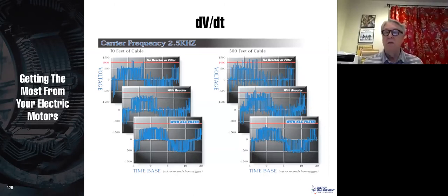DVDT, of course, stands for differential of voltage with respect to time, or derivative of voltage with respect to time. All it really means is it reduces the rise time. DVDT means how fast is the voltage changing. So look at here, here's one particular motor with one particular drive, and it's got 70 feet of cable between the motor and the drive.